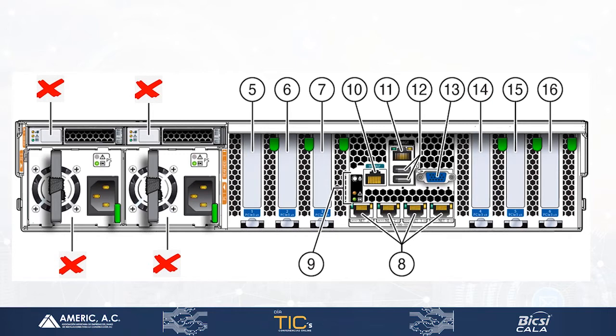But it also has a substantial impact on energy performance, because if you're running two power supplies in what we call a 2N mode, you can never utilize either of the power supplies by more than 40%, because when one fails, the other has to take the full load. So these power supplies never run higher than about 40% utilization in 2N mode, and at 40% utilization they're not very efficient — you get lots of heat loss from them. So that's a big deal.